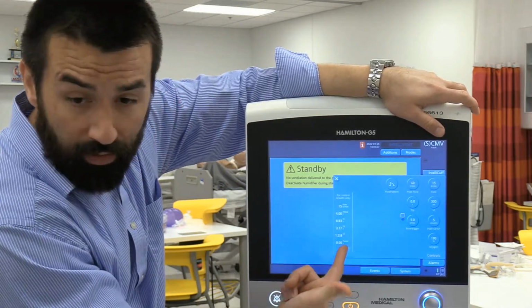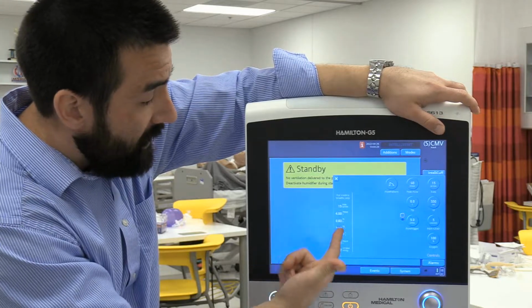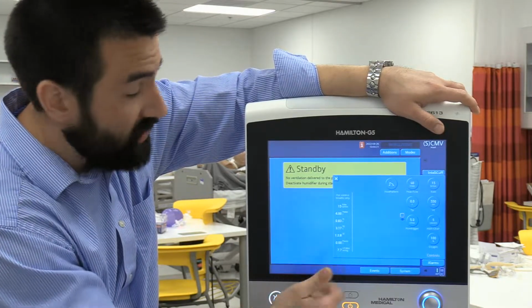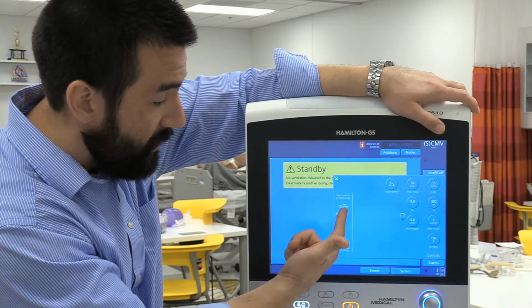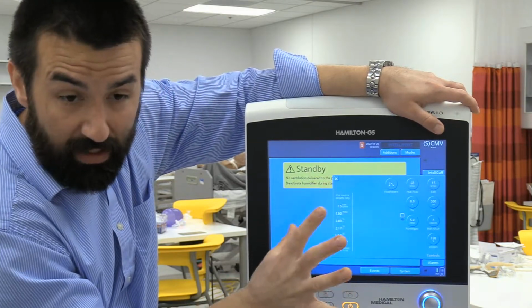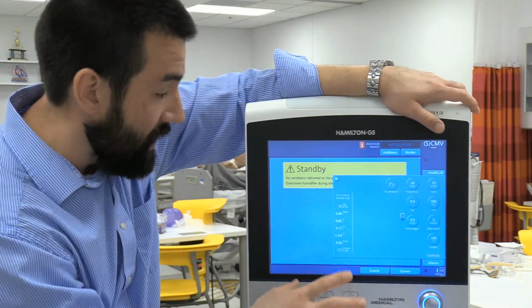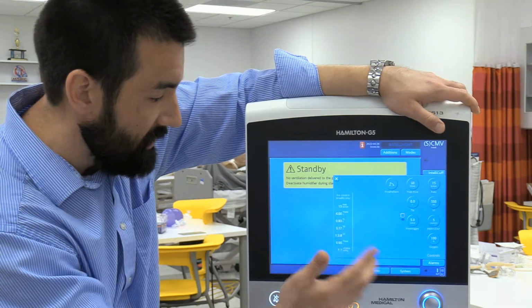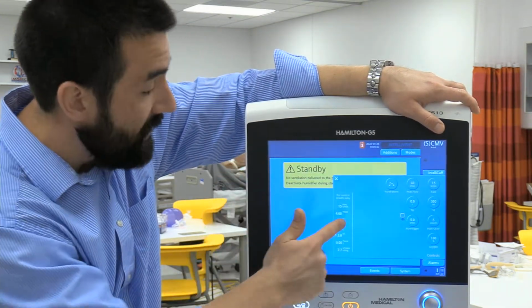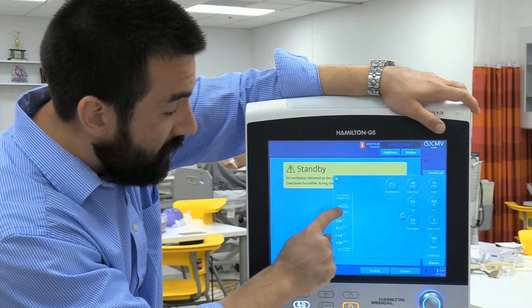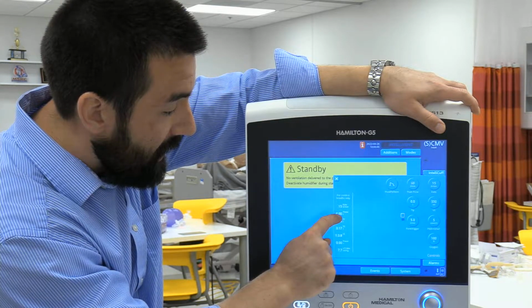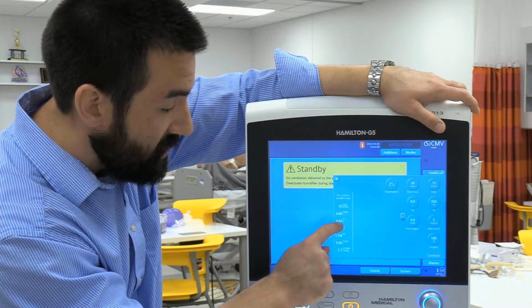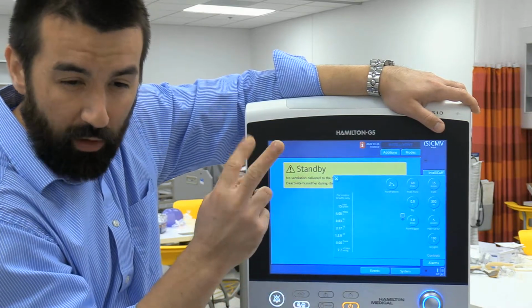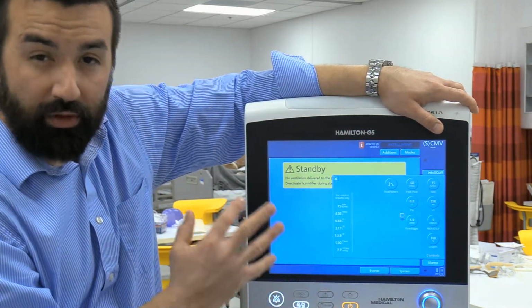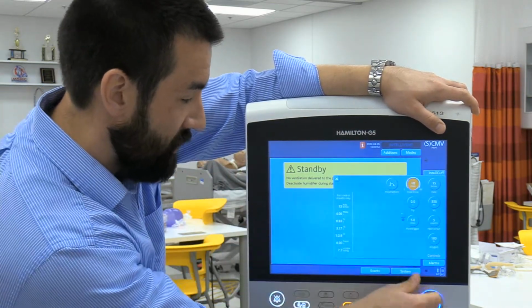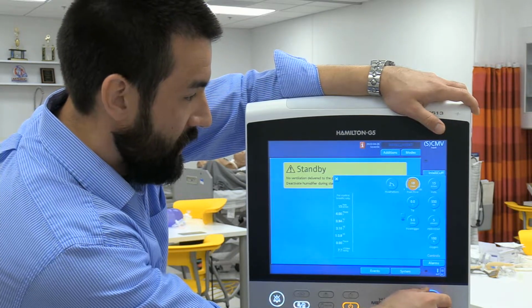All right. One thing I'll point out, all the different things that you should be able to calculate could also be found over here on the side. So your rate, and this is just based upon, if the patient's not breathing faster, obviously some of this stuff would change, like your E time and cycle time if they're triggering faster. So rate of 15 on these current settings, you've got a total cycle time of 4 seconds. Here's what your I time would be. So if we change our flow rate, our waveform, or our tidal volume, you'd see that change in real time here.